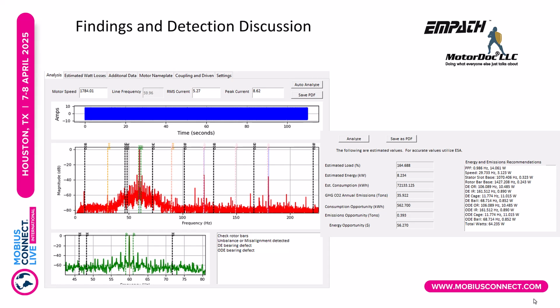Knowing what those are, knowing what the voltage is for the machine, and knowing what the bands are for what's allowed to be on the machine for voltage, we can make some assumptions so that we can use watts and energy to do some calculations to see how severe conditions are. So on this particular machine, as we look down at the pole pass frequency, it says check rotor bars, and we're at -40, which is actually pretty severe. It's only 14 watts of loss.